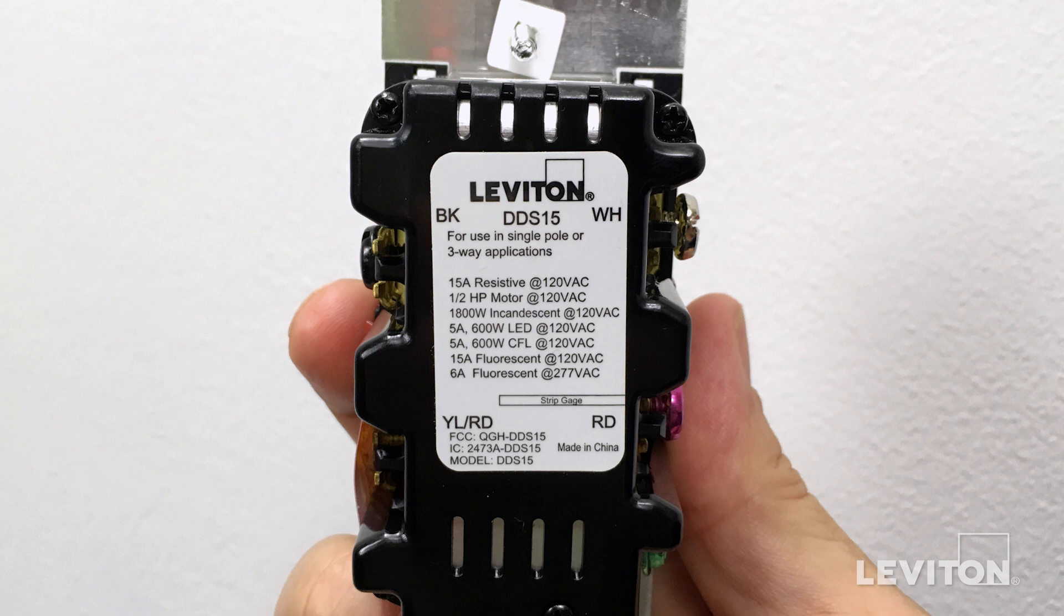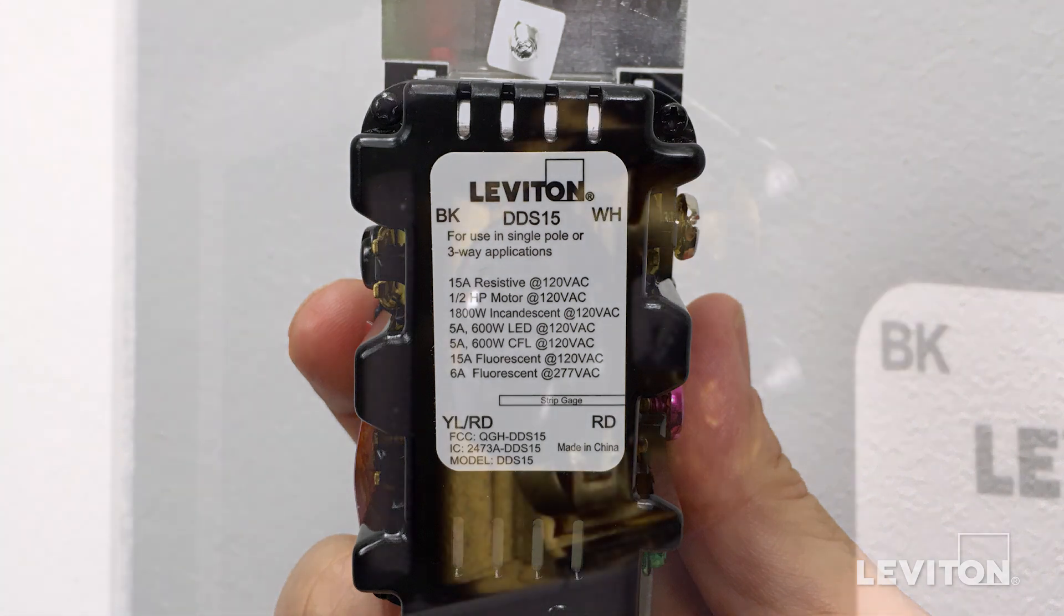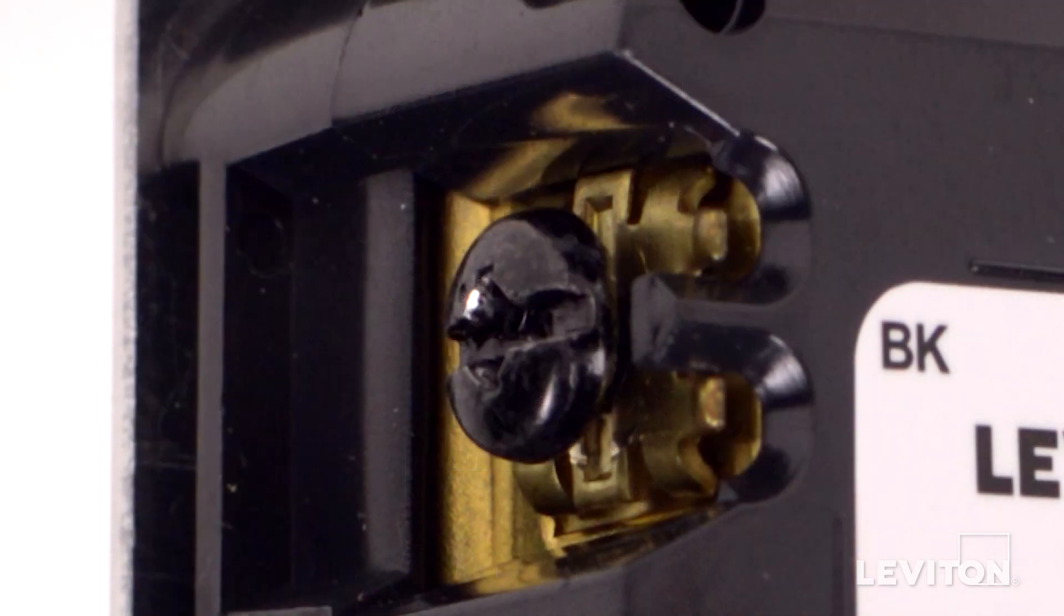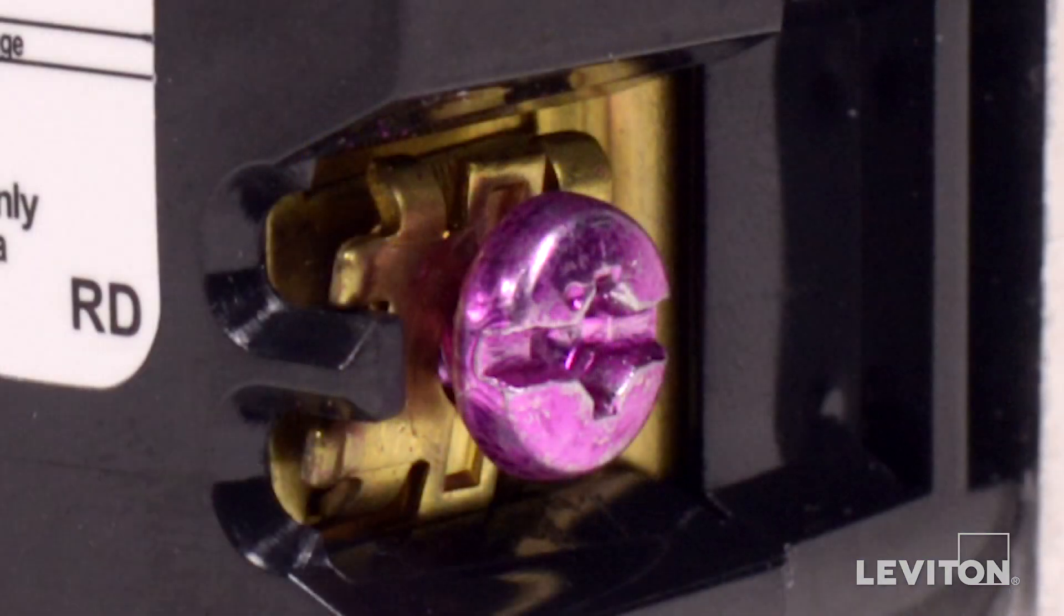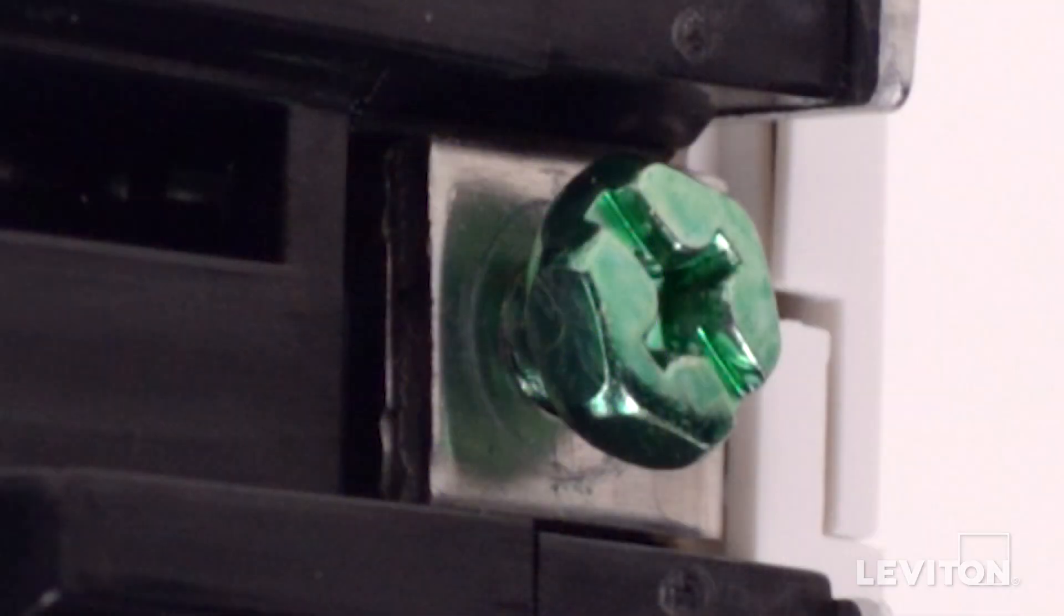Before wiring, it's important that you identify the terminal screws on the device to ensure that you are wiring it correctly. The black or BK is for the line or hot wire. The silver or WH terminal is for the neutral wire. The red or RD terminal is for the load. And the green terminal is for the ground wire.